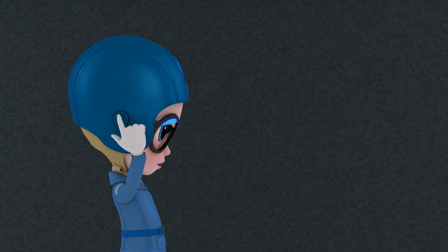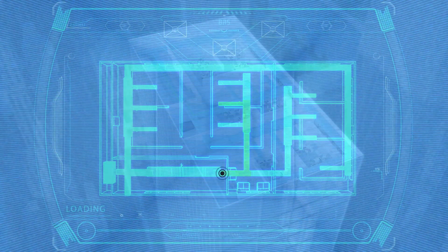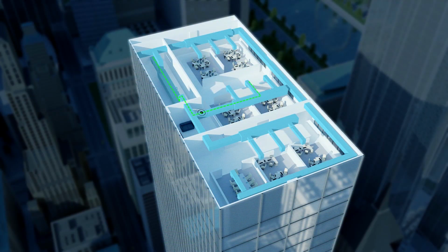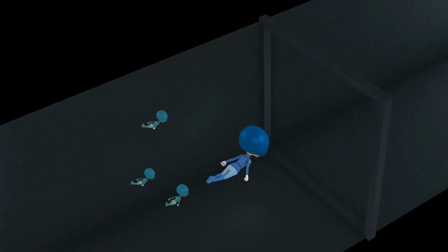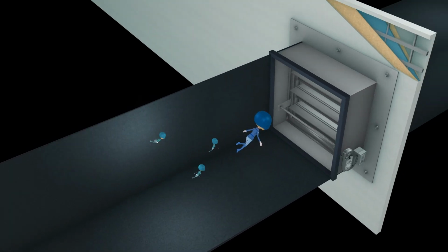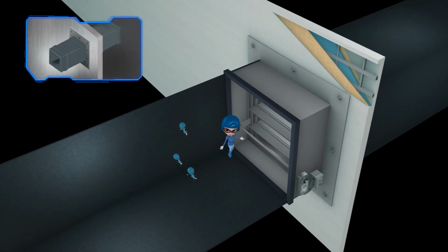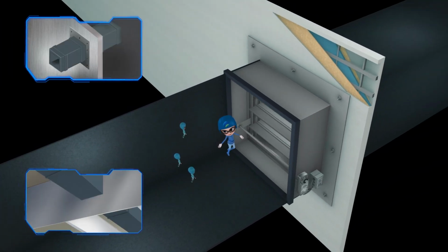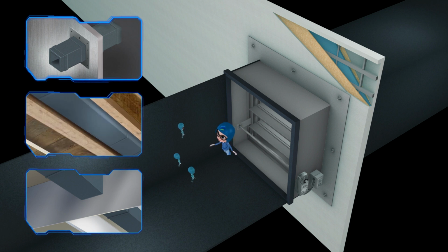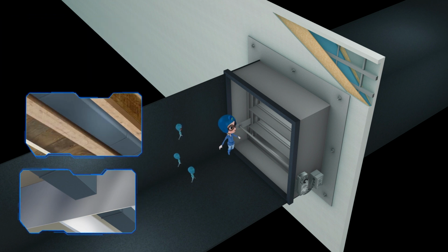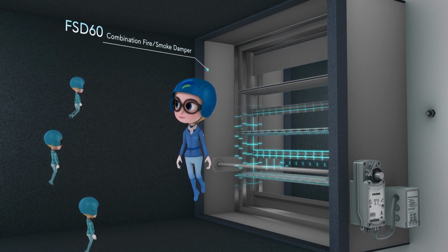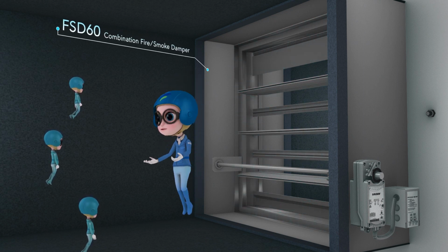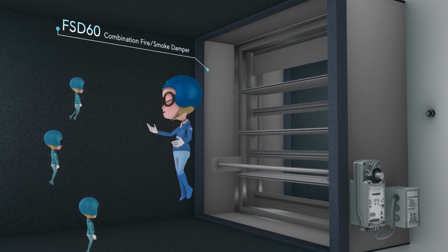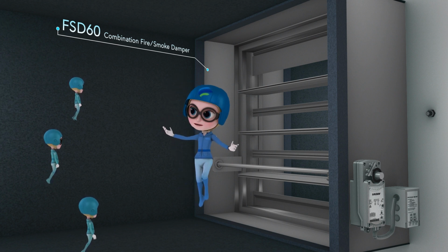Ducts are a series of tunnels that act as passageways for conditioned air to move through the building. Ducts within a building will often penetrate through fire-resistive rated features, such as fire partitions, smoke barriers, or even floor-ceiling assemblies, to name a few. When this happens, life safety dampers, such as a fire smoke damper, are required by the building code to protect the air duct opening at that location.